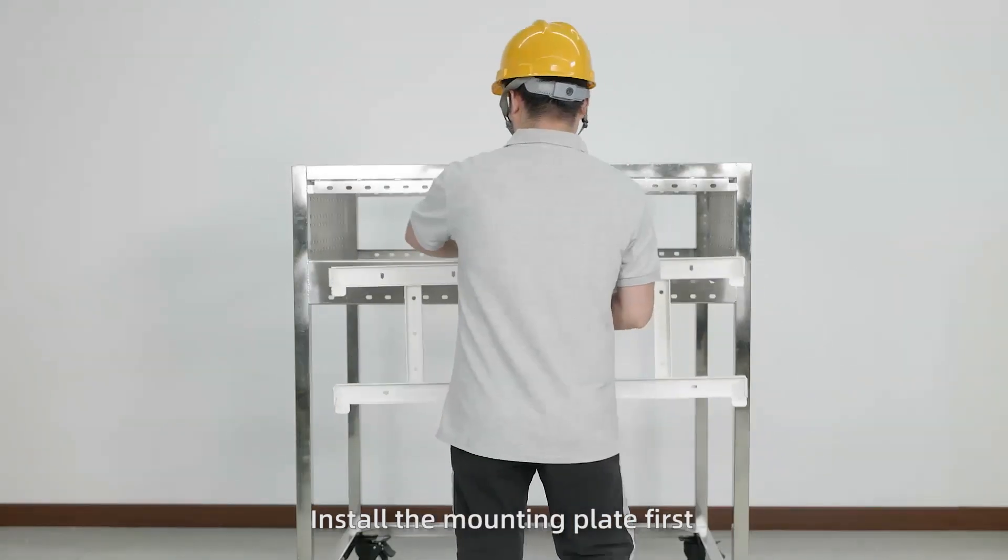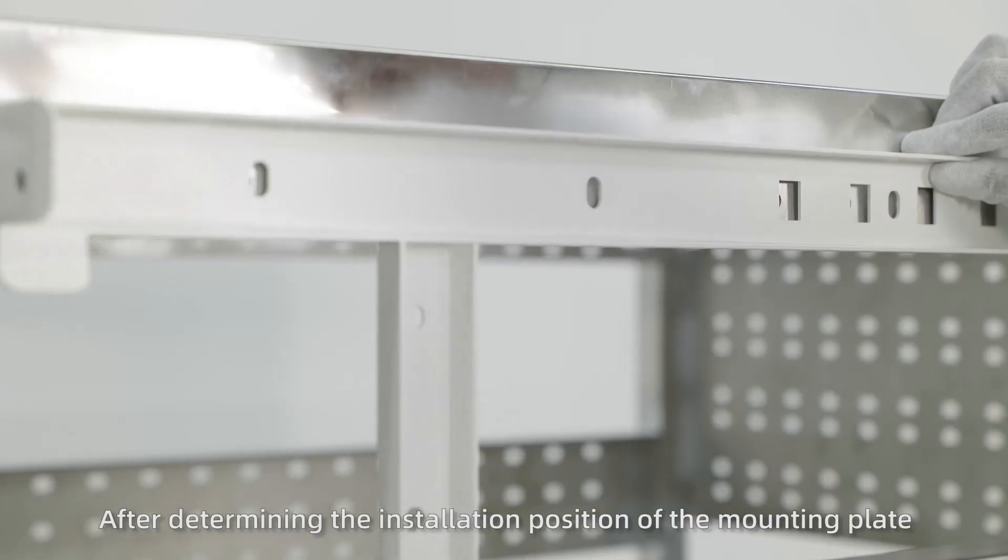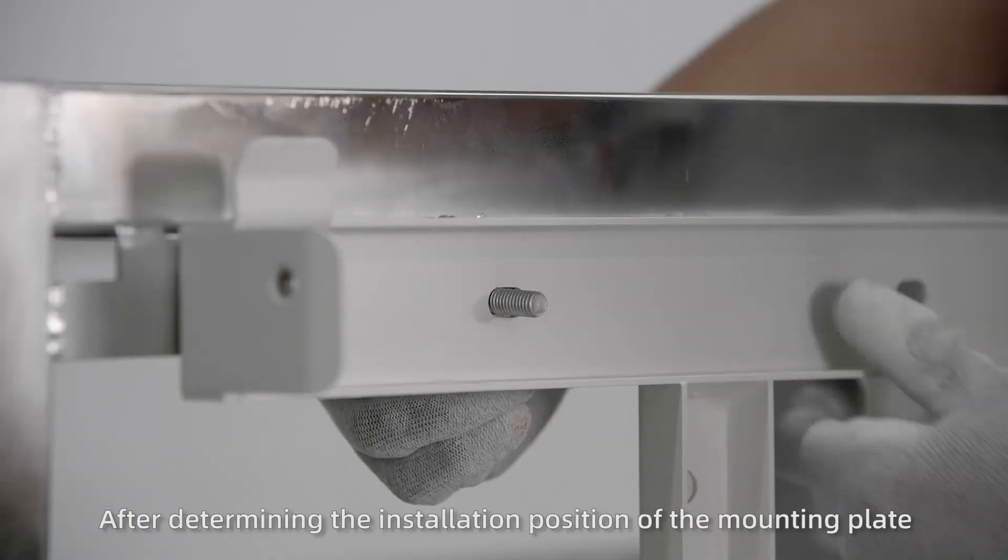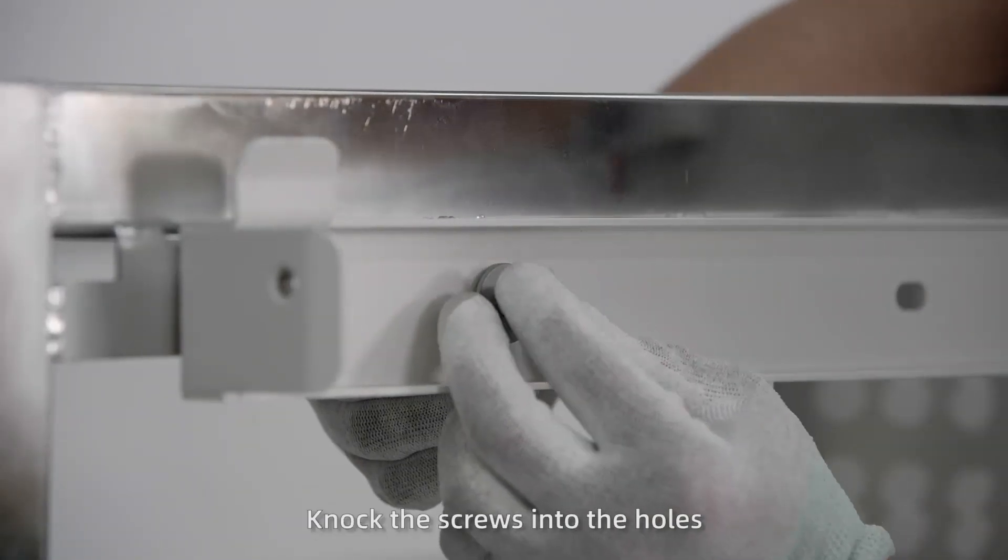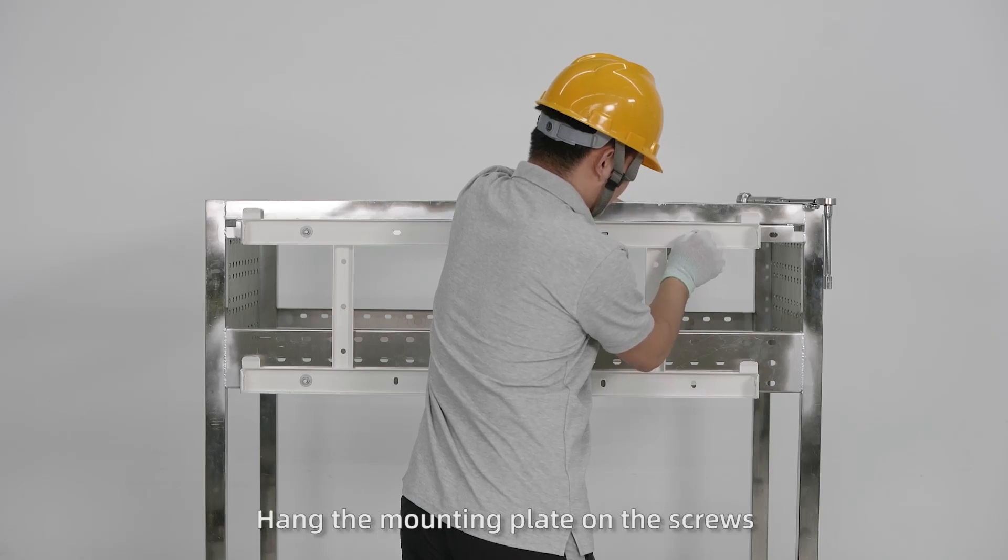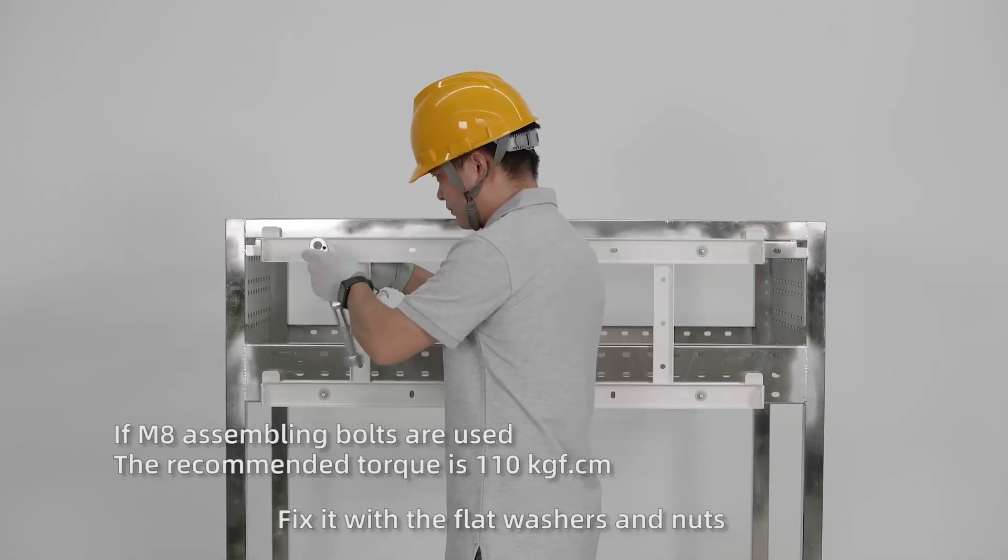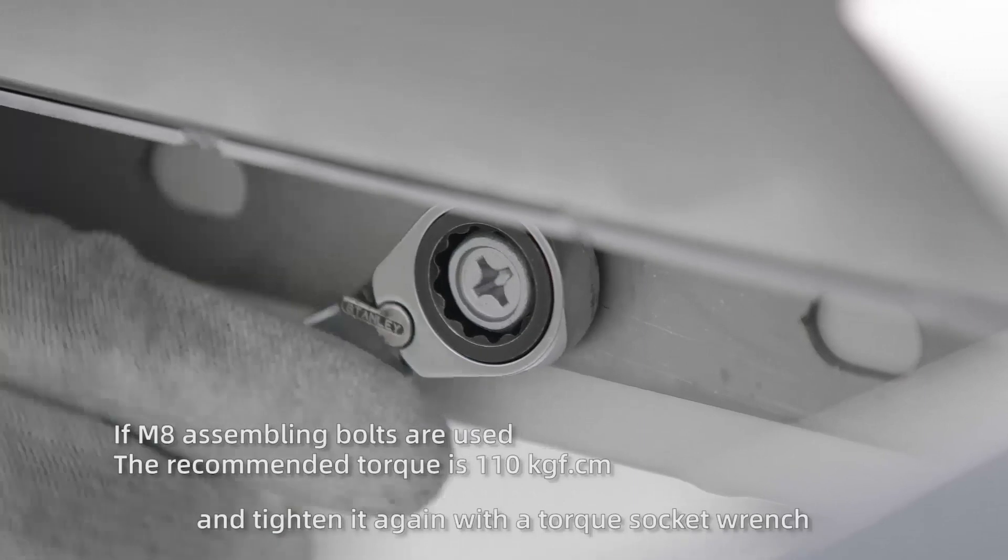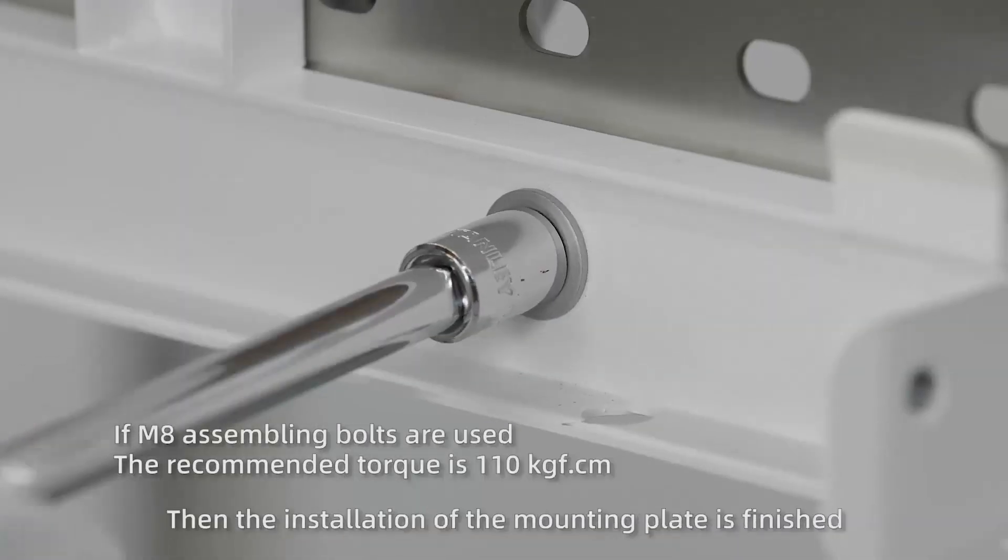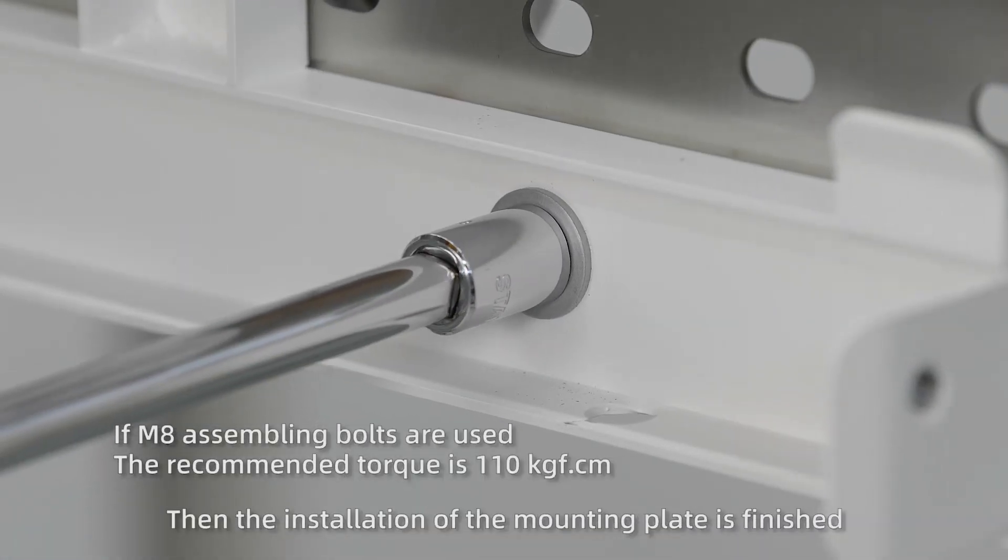Install the mounting plate first. After determining the installation position of the mounting plate, knock the screws into the holes, hang the mounting plate on the screws, fix it with the flat washers and nuts, and tighten it again with a torque socket wrench. Then the installation of the mounting plate is finished.